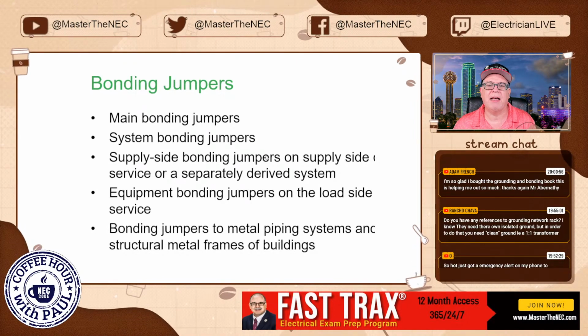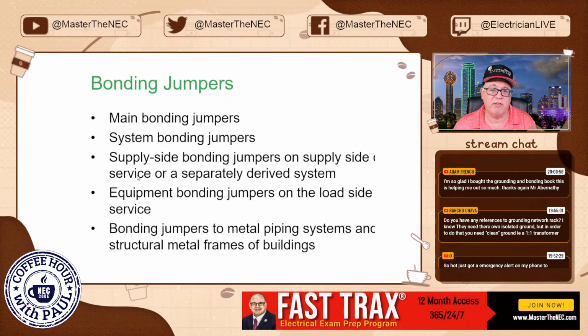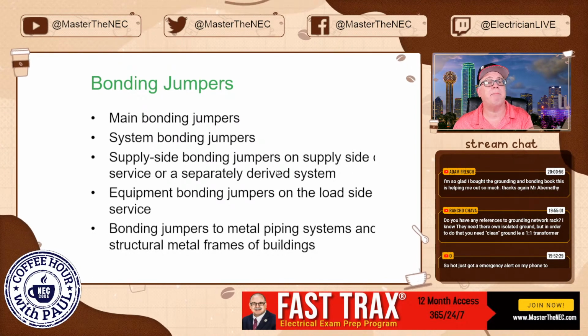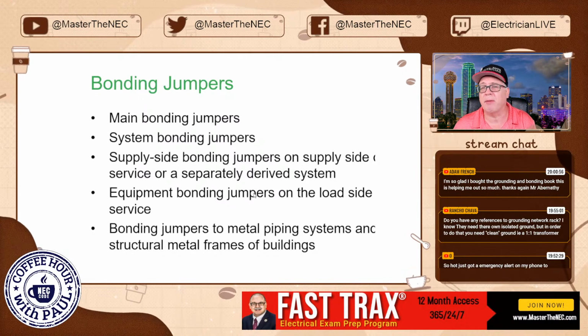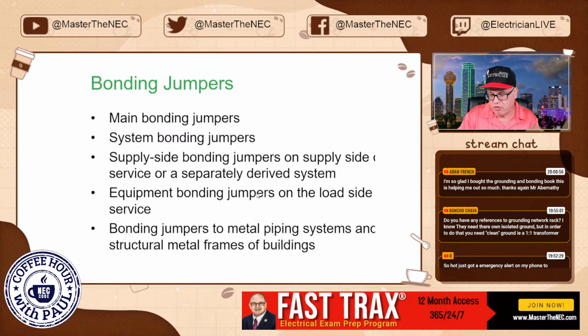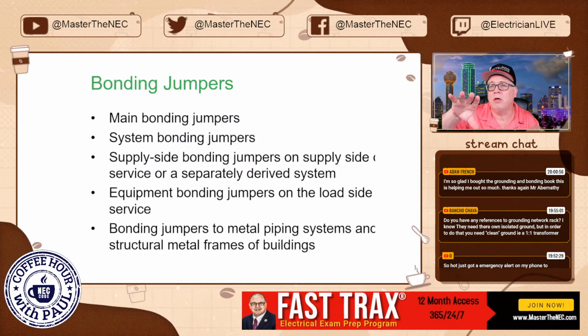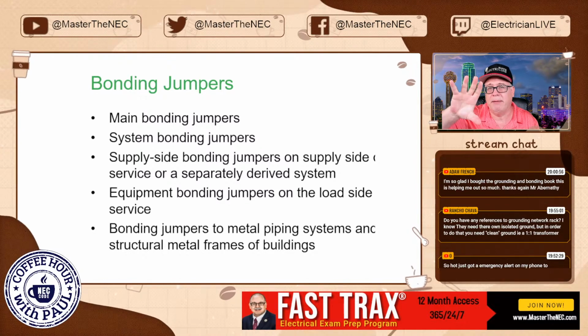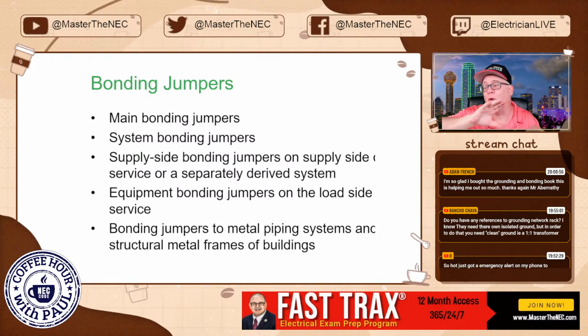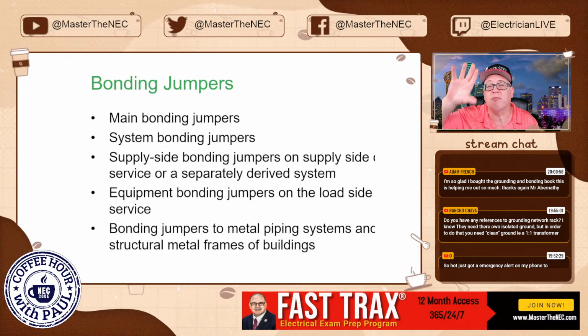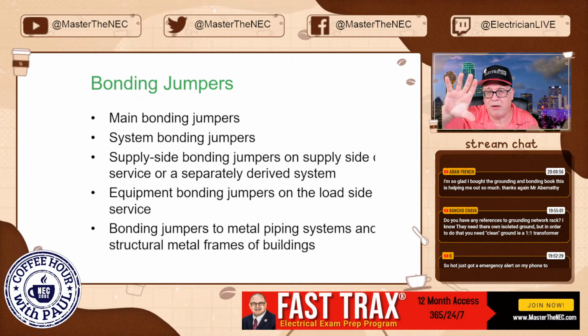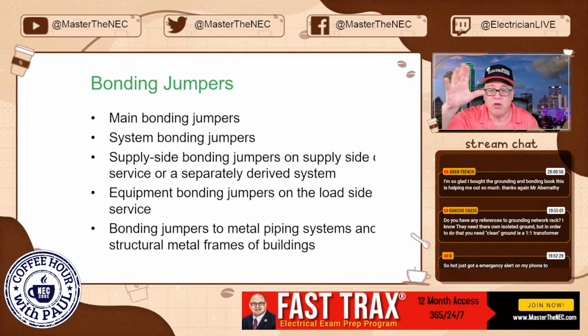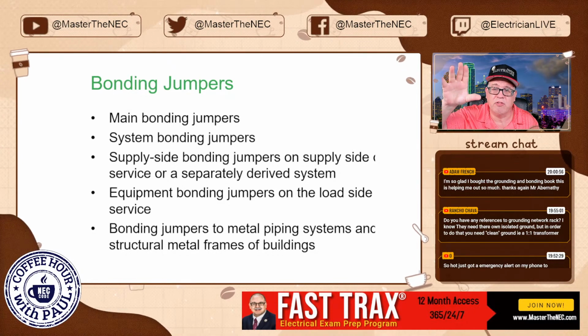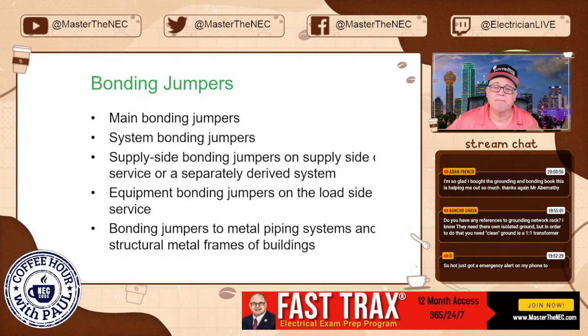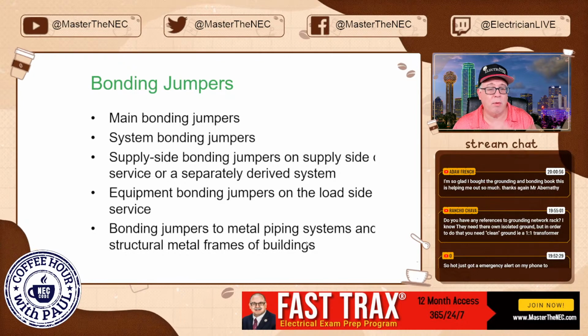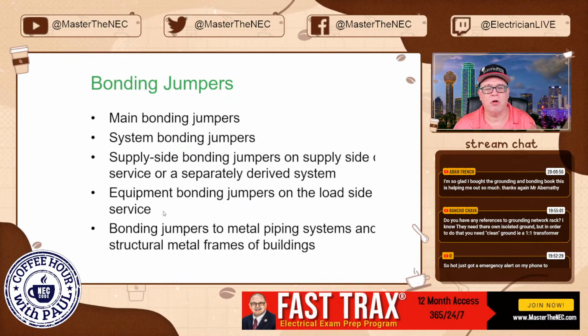Now, you have supply side bonding jumpers. They're on the supply side of a service. But you also have supply side bonding jumpers on the supply side of the separately derived system that might be going from the transformer secondary up to the service equipment. I mean, not service equipment, excuse me. Going from the secondary side of the transformer up to the remote distribution panel on the secondary of that transformer. You could have what's called a supply side bonding jumper there as well, okay? You have equipment bonding jumpers. We just saw a picture of that. That's on the load side of the service.